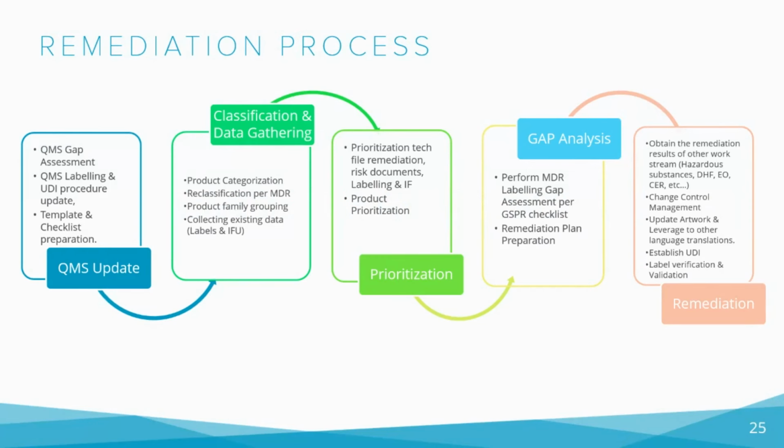The EU MDR introduced several new requirements for medical device labeling, including the inclusion of unique device identification (UDI), which identifies the device and provides information on its manufacturer, model, and other relevant details. The labeling remediation process involves a review of the device's existing labeling to identify any areas where it may not meet the requirements of the EU MDR.